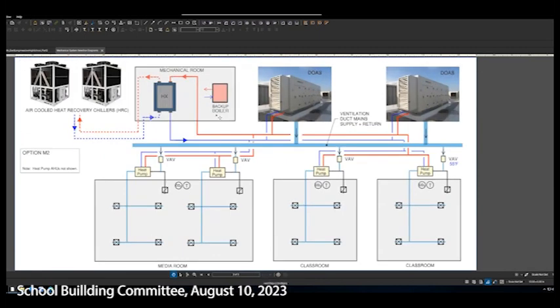The last option is a variation on the geothermal theme. Replace the idea of those in-ground geothermal fields with outdoor units called air-cooled heat recovery chillers. It's basically another kind of air-cooled heat pump. This is a way of providing heat to a loop or rejecting heat from a loop. It's connected to a heat exchanger the same way as the geothermal, and it's exactly the same in terms of how it distributes out through the building as the geothermal option.